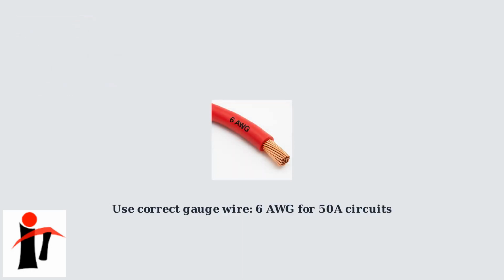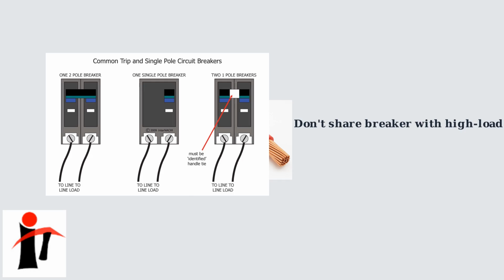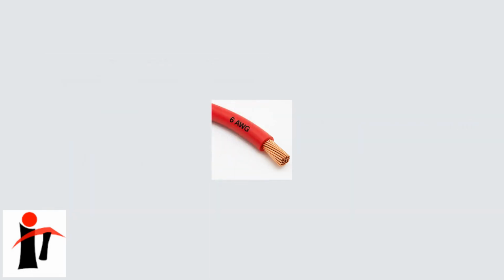Ensure you're using the correct wire gauge for your circuit. For 50-amp circuits like Gen 2 wall connectors, use 6 AWG wire. Using undersized wire can cause voltage drops and overheating, leading to breaker trips. Make sure the breaker isn't shared with other high-load devices like electric stoves or air conditioners. Shared breakers can overload the circuit, causing frequent trips. Use dedicated breakers rated for at least 50 amps, or 60 amps for Gen 3 models.